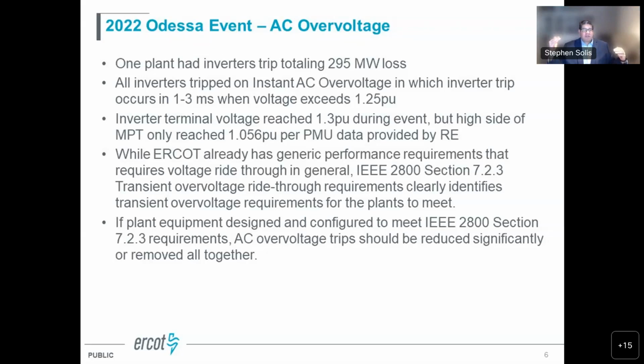You have to be able to ride through, so you have to account for any voltage rise between the point of interconnection and the inverter terminals. And when we looked at this particular scenario, the inverter terminal voltage was 1.3 per unit. On the high side of the main power transformer, 1.056 per unit. So we see a pretty big delta. And while ERCOT already does have a performance requirement to ride through, the transient overvoltage ride-through requirements identified in Section 723 of IEEE 2800, well, they're more transparent.